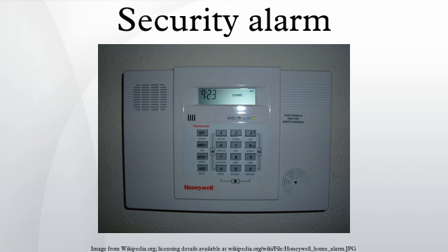Broadband alarm monitoring. Increasing deployment of voice-over IP technology is driving the adoption of broadband signaling for alarm reporting. Many sites requiring alarm installations no longer have conventional telephone lines, and alarm panels with conventional telephone dialer capability do not work reliably over some types of VoIP service. Dial-up analog alarm panels or systems with serial parallel data ports may be migrated to broadband through the addition of an alarm server device which converts telephone signaling signals or data port traffic to IP messages suitable for broadband transmission.